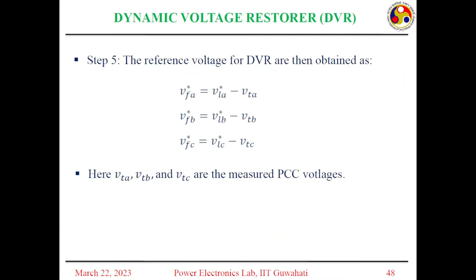Now we have a third device called Unified Power Quality Conditioner, where we unify the objectives of both D-STATCOM and DVR. It has both shunt compensation and series compensation. So basically, if you have a PCC here, the voltage source represents DVR operation, that is series compensation, and the current source represents the D-STATCOM functionality, that is shunt compensation. These two are coupled to each other.